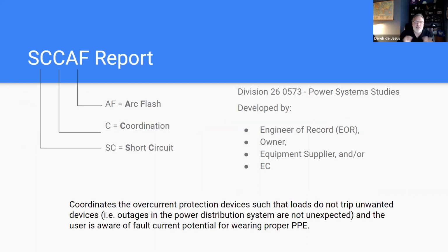So let's start with some definitions. This is an acronym that if you Google it on the internet, you may not come across it. You might actually see something called a coordination study or a short circuit study or an arc flash hazard analysis. Well, all of those documents make up a SCCAF report. The short circuit, the coordination, and arc flash analysis come out of a requirement in the contract documents.